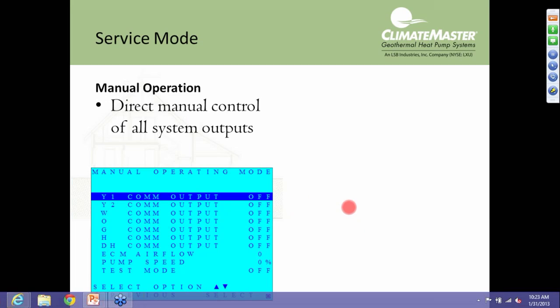All right, so let's take a look at manual operation. In manual operation, you can give the unit specific calls. Not only can I turn on Y1, Y2 for second stage compressor operation, I can also go down here to pump speed and tell the pump a specific speed I want it to run. Here in a little bit, we're going to talk about commissioning these heat pumps. When we commission one of these heat pumps, we now recommend going through manual operation, giving the pump a specific speed. It may take 2 or 3 tries getting the speed that we want to get the actual water flow that's on our specifications for that unit.